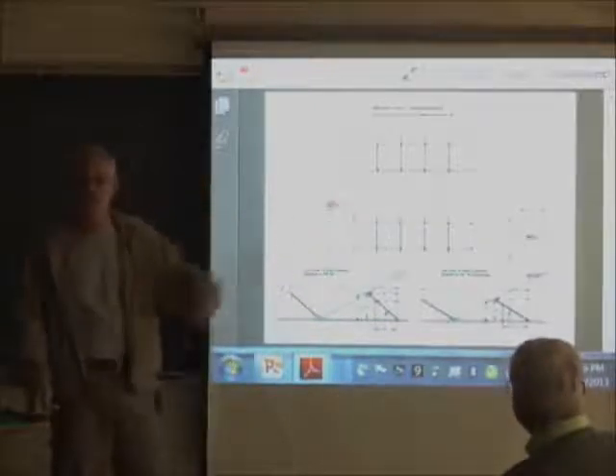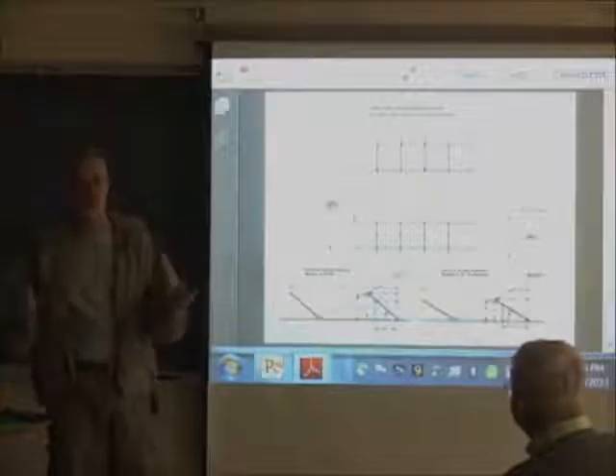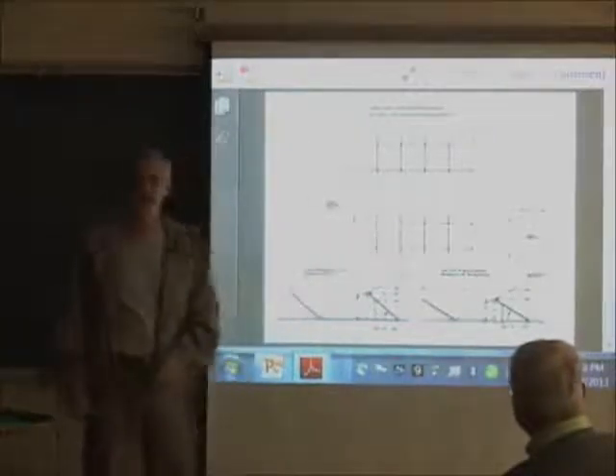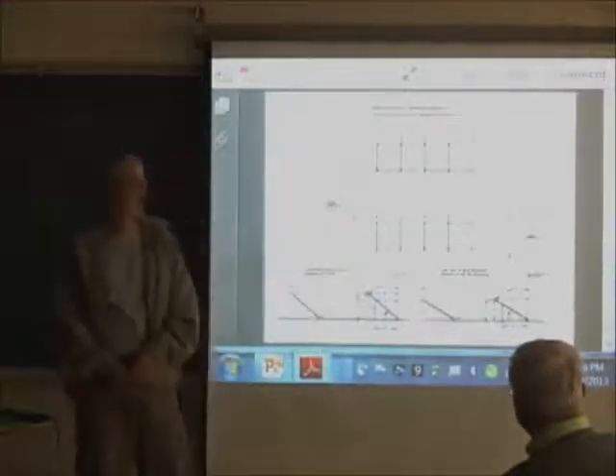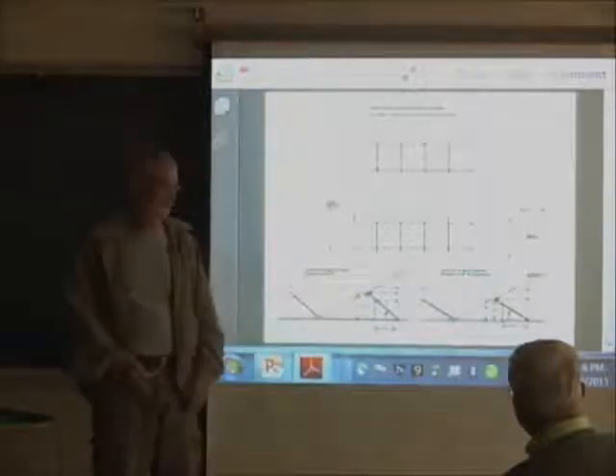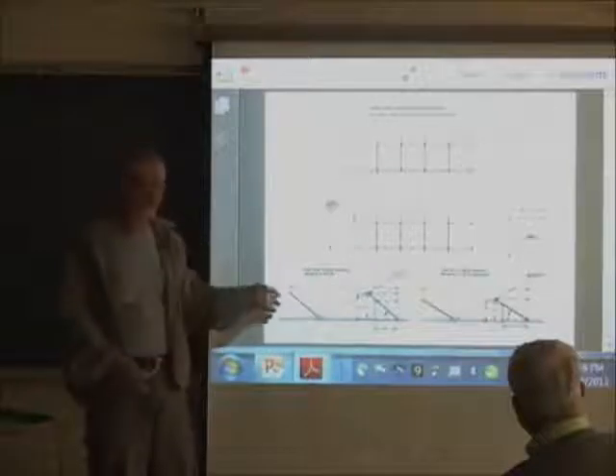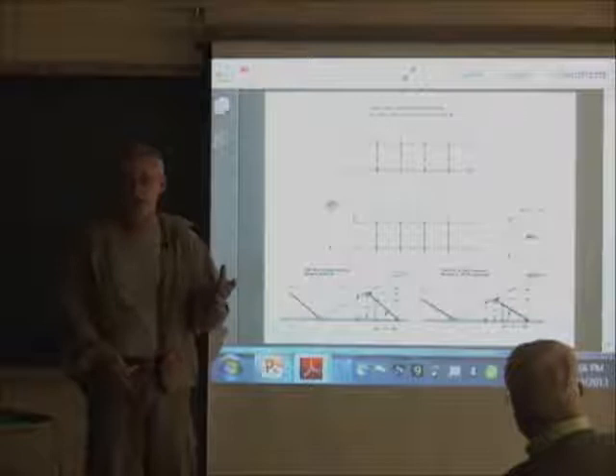The cells are in series, and if you interrupt the voltage from one of the cells in the series, you've got 0 volts. Most panels have bypass diodes that say, okay, that one's dead, but at least we can run the others in the row. But shadow from this front row could actually shut down the back row. In practice, professional designers will actually allow that to happen a month out of the year.